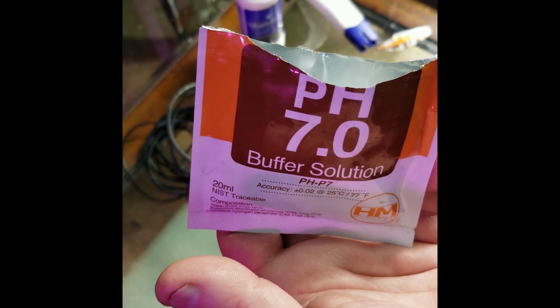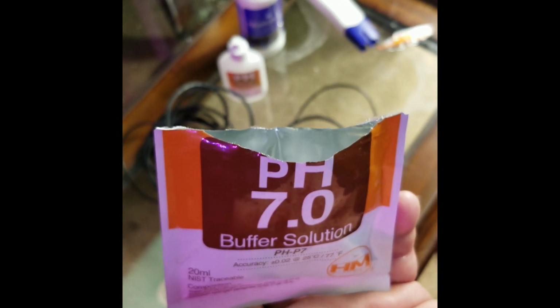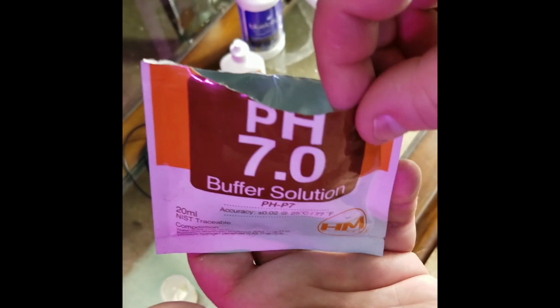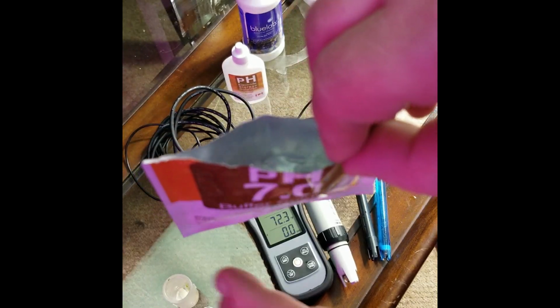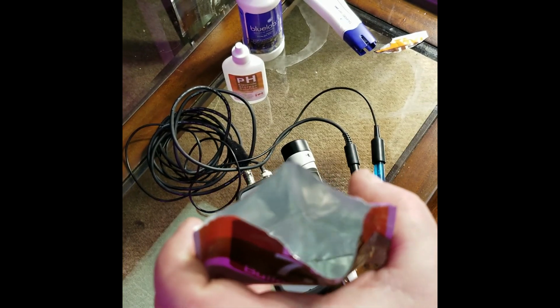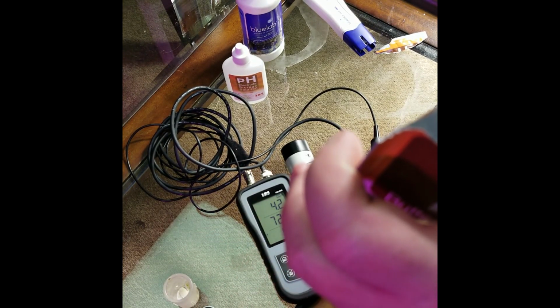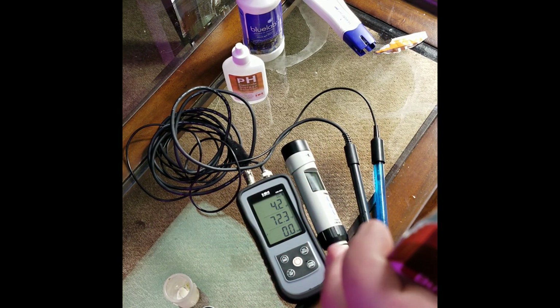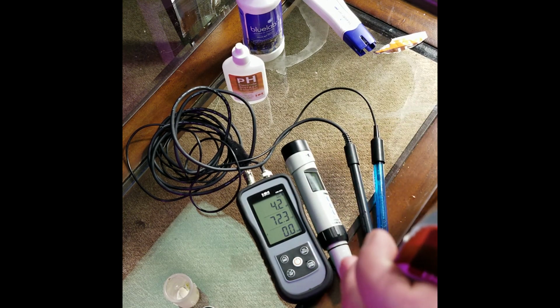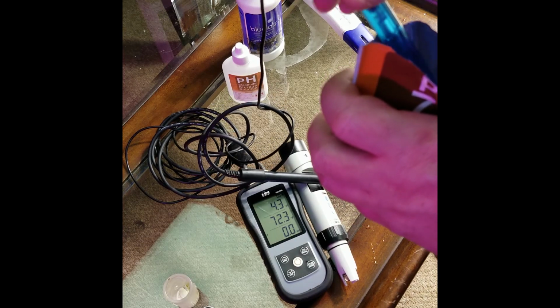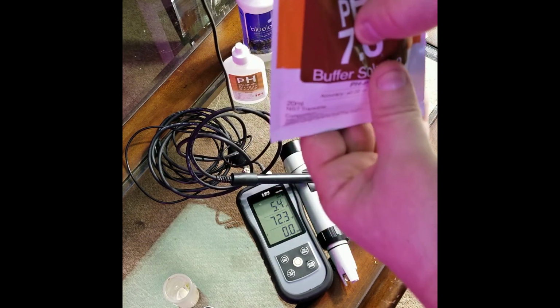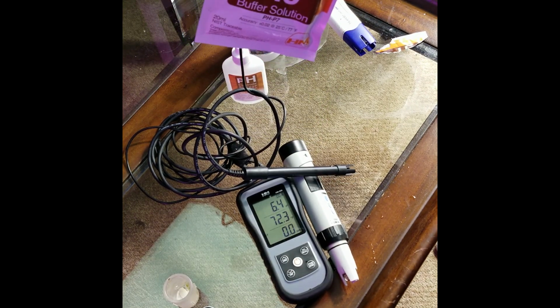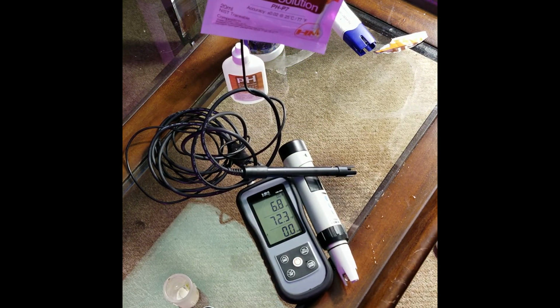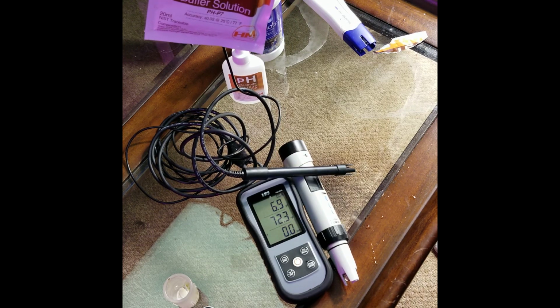If not, if it seems to be stable, but it definitely seems like it's off, start with a pH of 7, because neutral is where you always want to start, which also has 0 ions, and it should start to balance out the glass in the probe to start. So with this one on, we're going to put the probe in the pH 7, and we're going to look. And this one should be pretty accurate. I use this specific meter out in the barn.